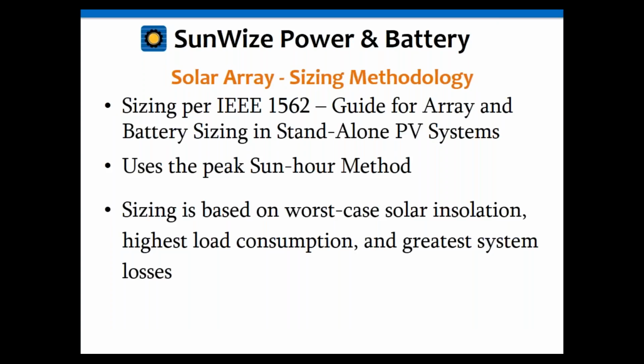Okay, the sizing methodology we're going to be using is the sun hour method, as I mentioned earlier. All of this is based upon IEEE standard 1562. That is the guide for array and battery sizing in standalone PV systems. I highly recommend, if you want to learn more or go into detail, it has a worksheet as well that you can use for going through the calculations and everything.